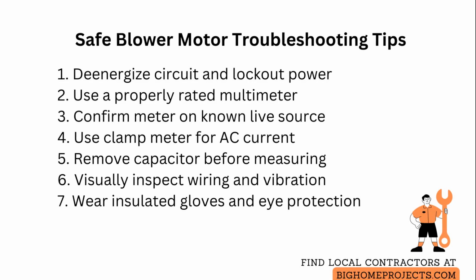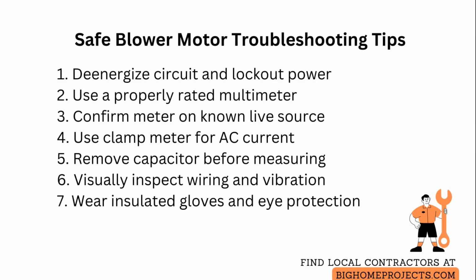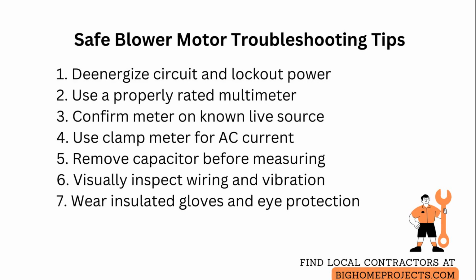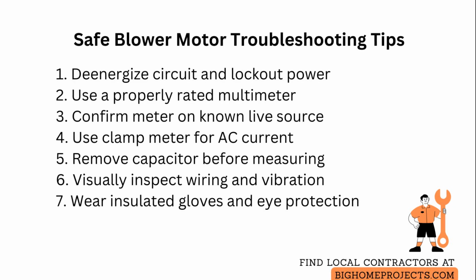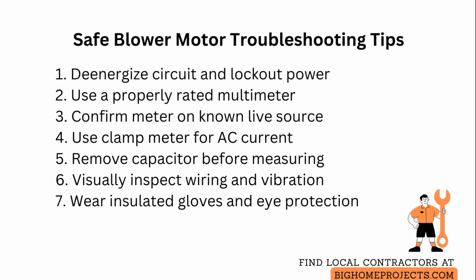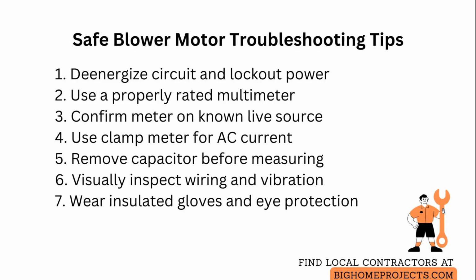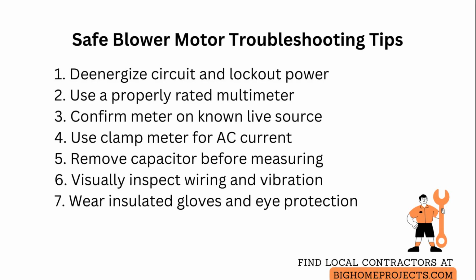If you must observe it running for diagnostic purposes, use a properly rated multimeter to measure voltage, current, and continuity. Set the meter to the correct range and test the leads to confirm the tool is functioning on a known live source before use. For current measurement, use either a clamp meter designed for alternating current or a meter with a current function and the proper probe placement, and never try to estimate current by feel or sound.